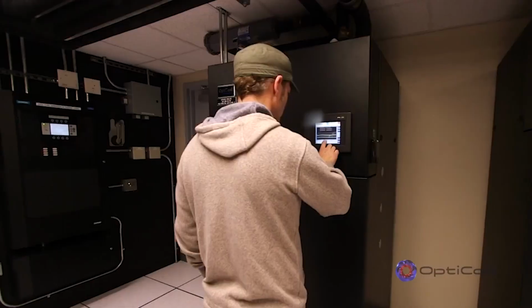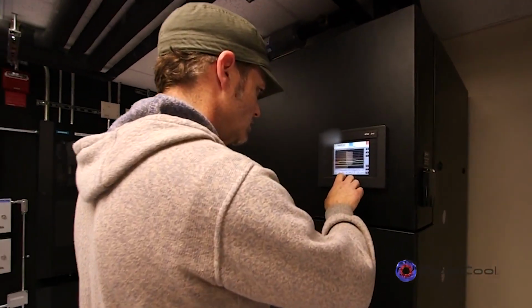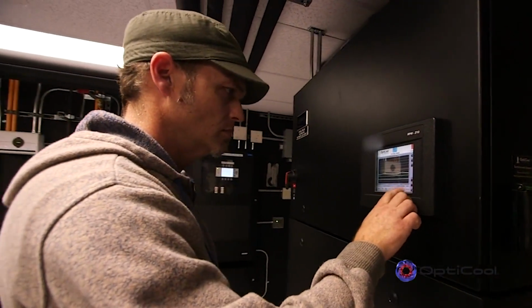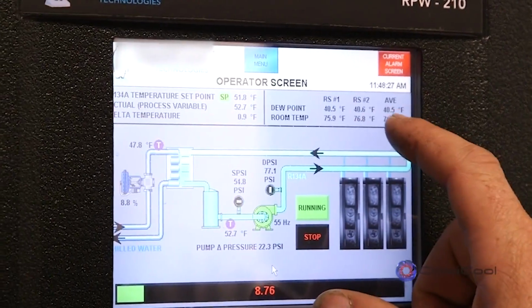I spend a lot more time in the conventional room dealing with hot spots and even cold spots from time to time, and cycling compressors and all kinds of things that come along with mechanical cooling. We don't have that in the OptiCool, because it's just a pump that pumps the refrigerant out and comes back with the heat already in it.